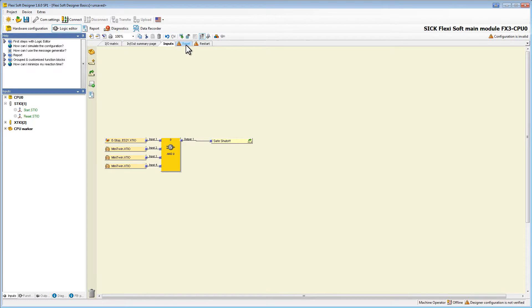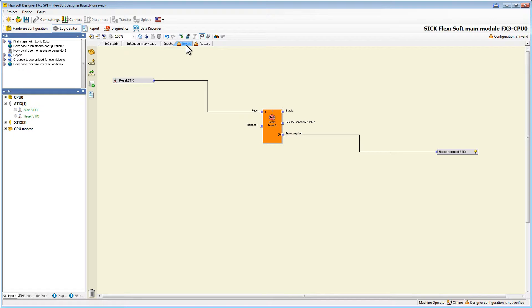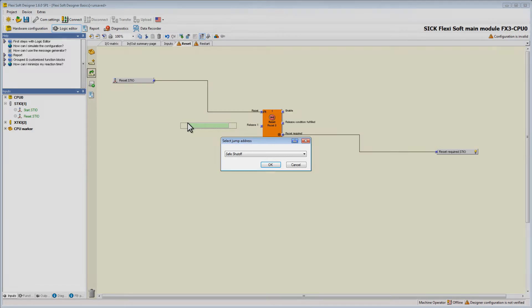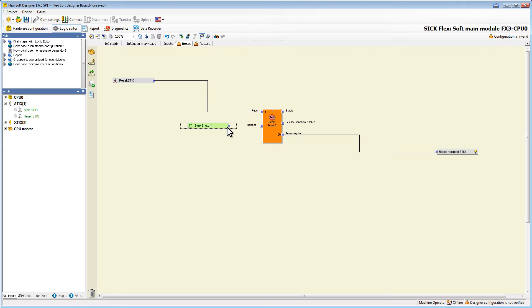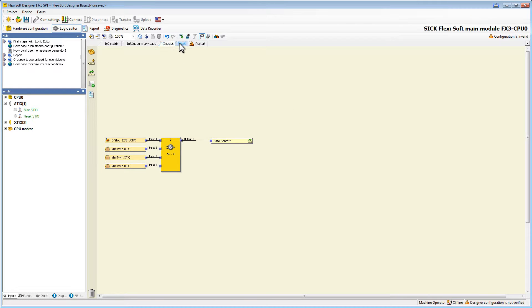After that we can wire it to the function block like every other output via simple drag and drop. On the second page, the reset page, we now need to connect the input of the reset block with our jump address we just created. To do this we drag the destination jump address to our logic. Again a window shows up and asks us to select a source address. In this drop-down menu we will find all available addresses. We choose 'Safe Shutoff' and click OK. If we now connect it to the release input of the reset block, it will be the same as if we had connected our end function block from the other page directly to it.